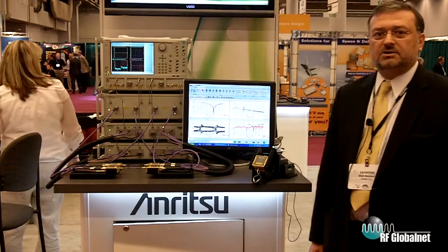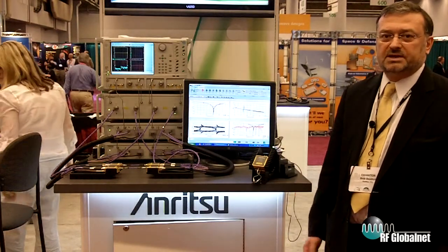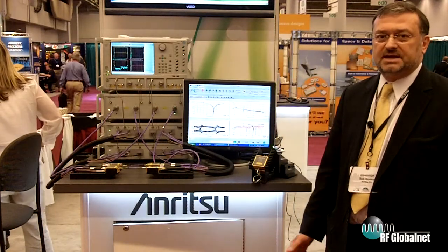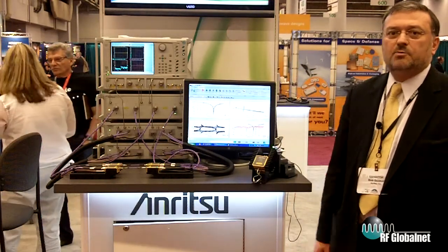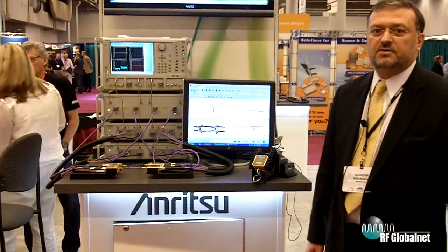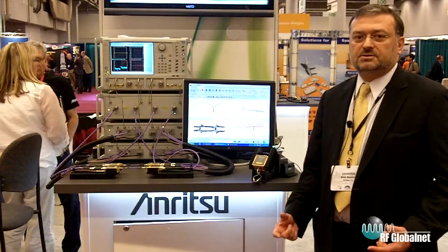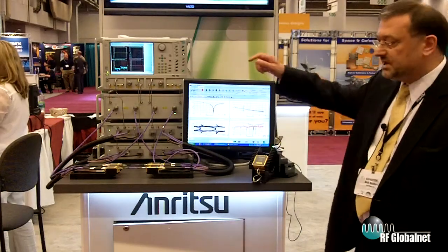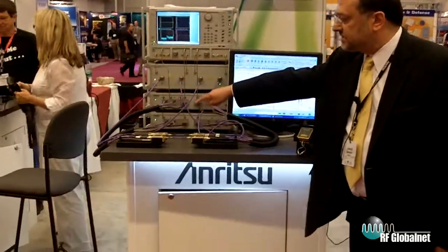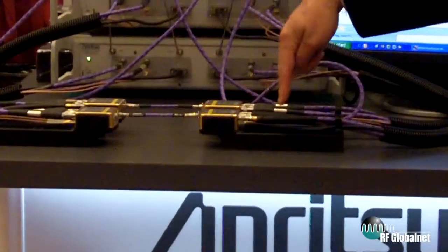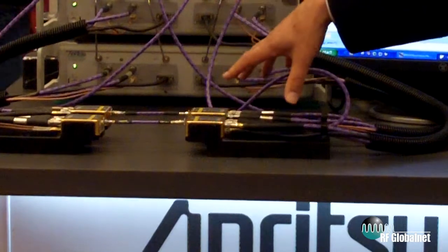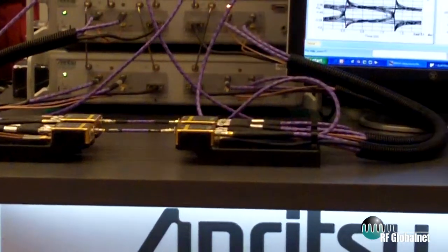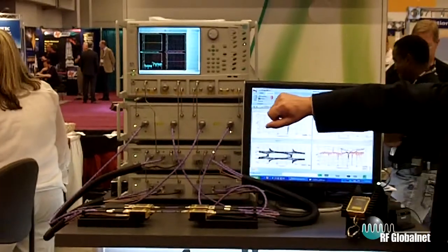So we've just looked at our technology demonstration of 140 gigahertz based on our earlier 110 gigahertz test heads for on-wafer test. We needed to go beyond that though. Just doing two-port measurements isn't enough. In many applications, people need to measure devices with 4 ports, whether this be for signal integrity measurements on differential pairs or devices like differential amplifiers, either characterized or on wafer. So what we see here is, for the first time, Anritsu's announcement of a 4-port version of our frequency extension modules to 110 gigahertz, connected up to our standard VectorStar analyzer and test sets.